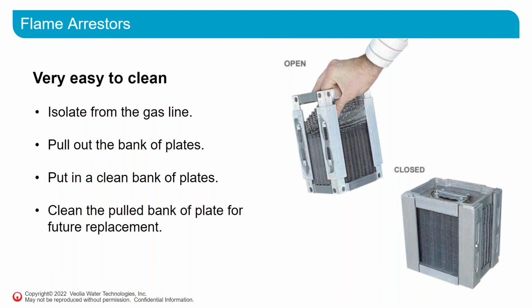So it's good to have a spare bank per size that's installed. For different size lines and different flows, different points of the system, you may have a different size flame arrestor. So for whatever you have, it's a good idea to have one spare for each size so that you always have a clean one that you can install if you have a clog or an issue. And then you can pull the affected one out and clean it and then have it on hand for future replacement.